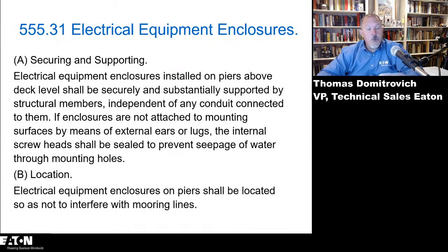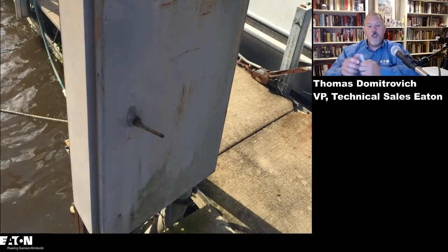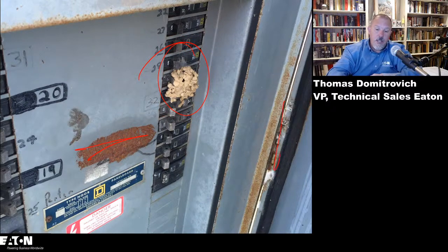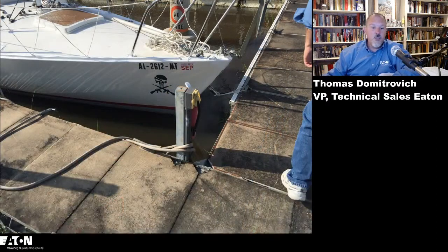555.31, securing and supporting electrical equipment: enclosures installed on piers shall be securely and substantially supported by structural members. So these are examples that you got to be mindful of what you're installing that on, and it's got to be substantial because this is an area that degrades over time. This is a panel that has seen a lot. It's all rusty. The hinges are rusty. The structure that it's supported by was rusty.